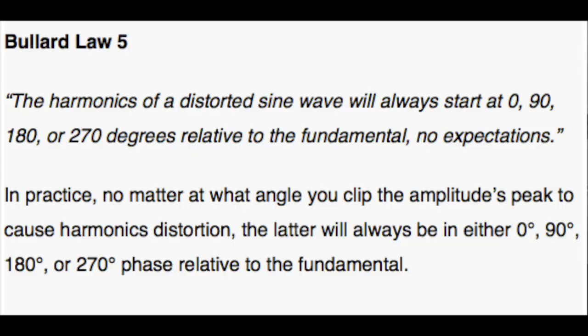I struggled with this for a long time trying to figure out how to extract the phases of the harmonics. Like I said, if you look at a distorted sine wave and look at the phase, you see a cloud of garbage — not really helpful. But if you extract everything that's a harmonic, get rid of all the noise, everything that's not a harmonic, and look at the phases of the harmonics, you get Law 5.